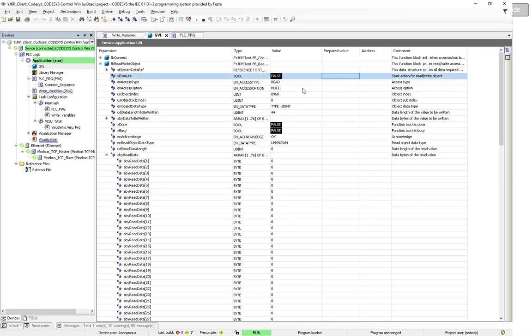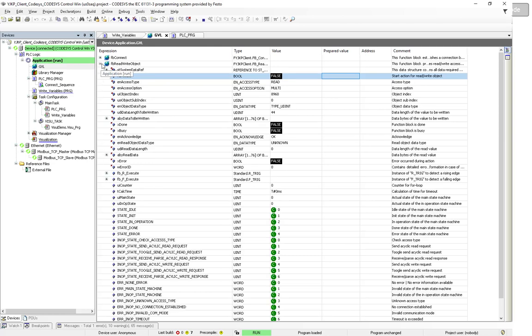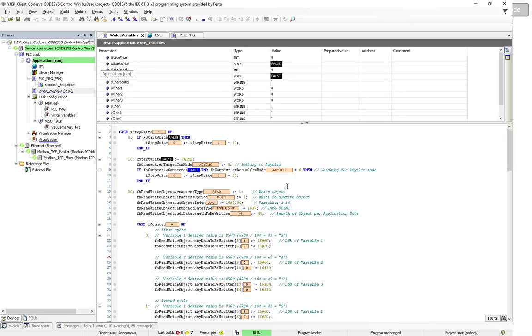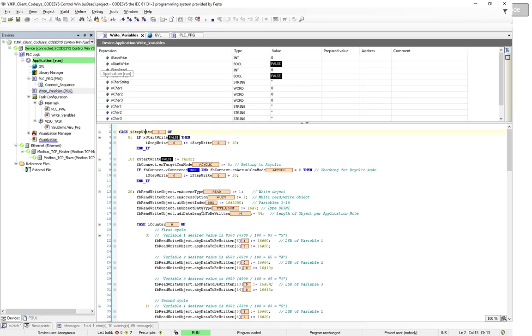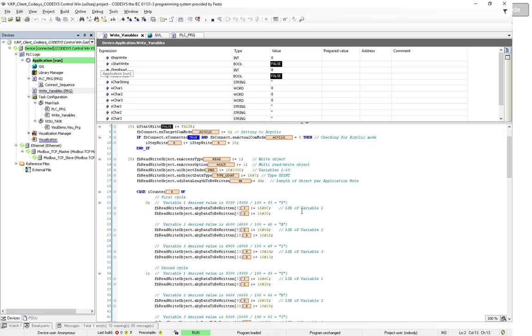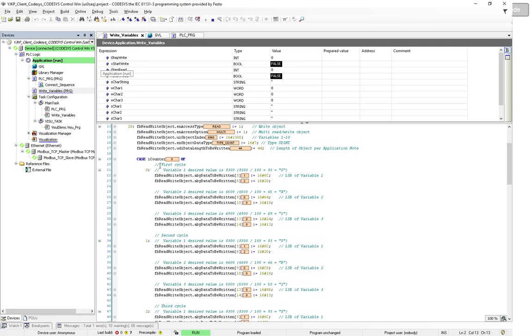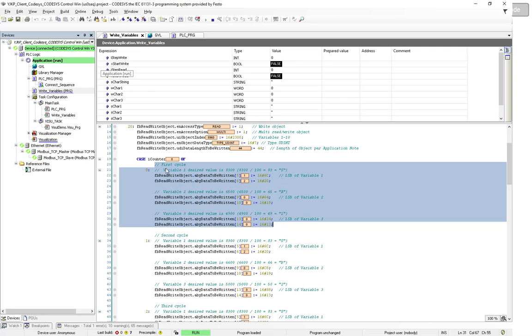I wanted to show that manually because I created a sequence that does this automatically, and I do this three times. In the program, I force a bit to write, go into a case statement, switch the communication mode to acyclic, check that connection is established, check that the actual communication mode is acyclic, and then do exactly what I just showed manually. I set the mode to write, multi-objects, set the index, data type, and data length to be written.